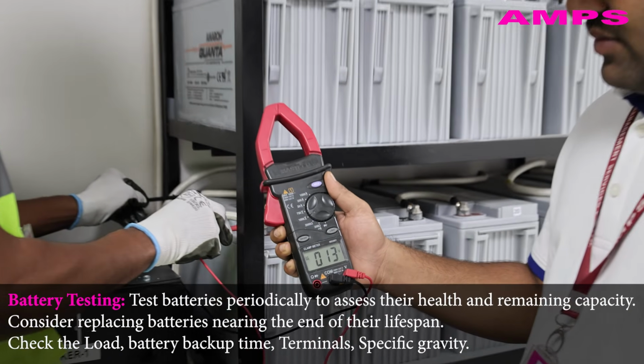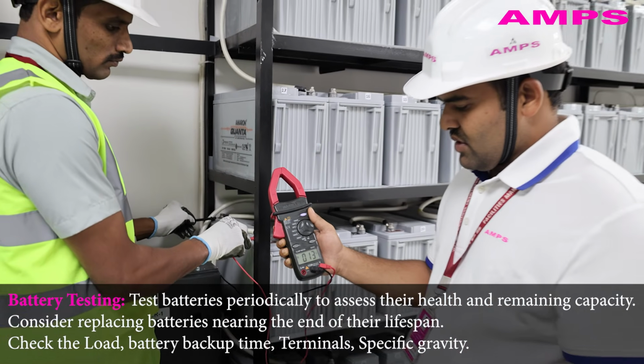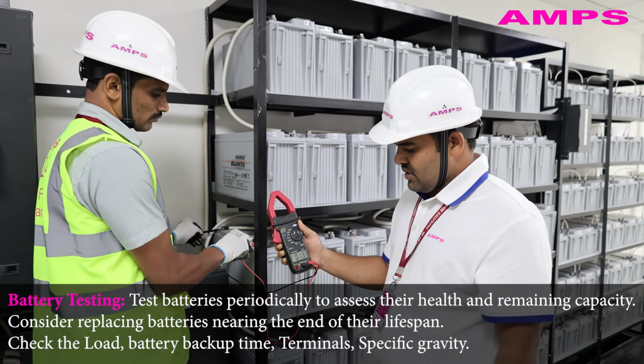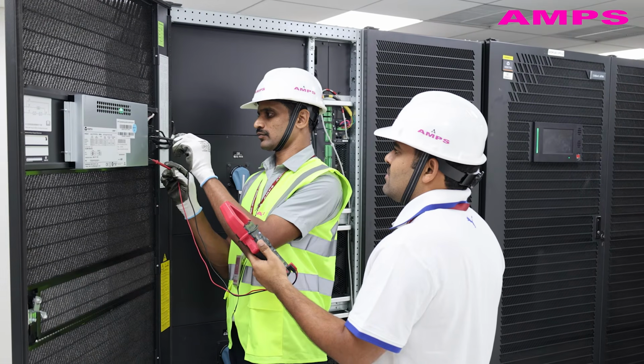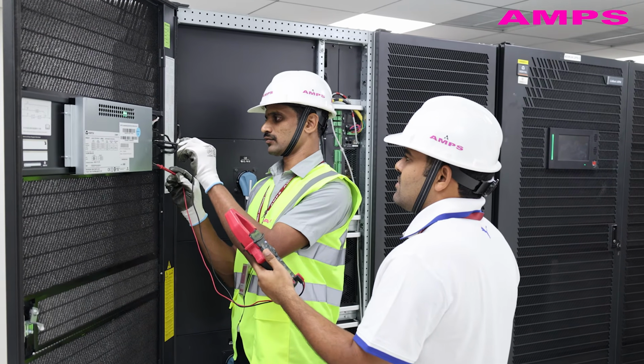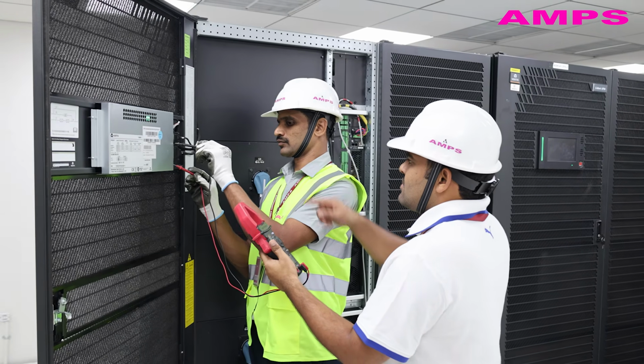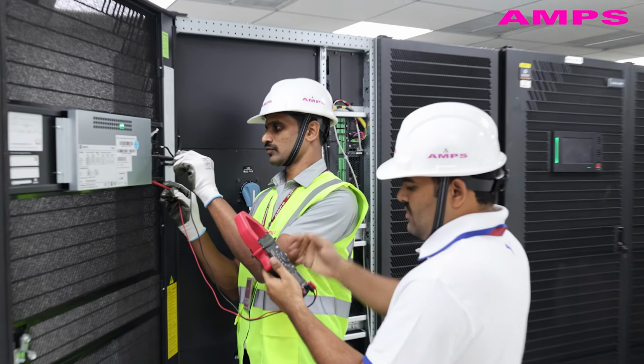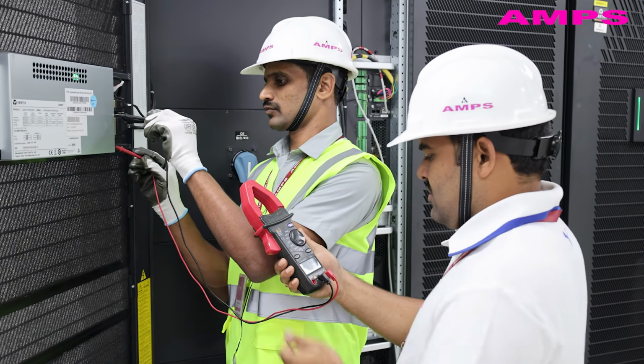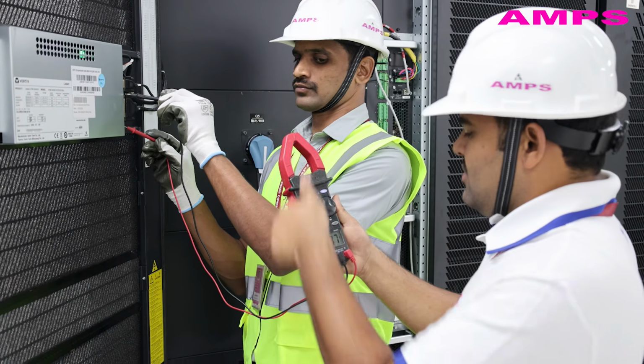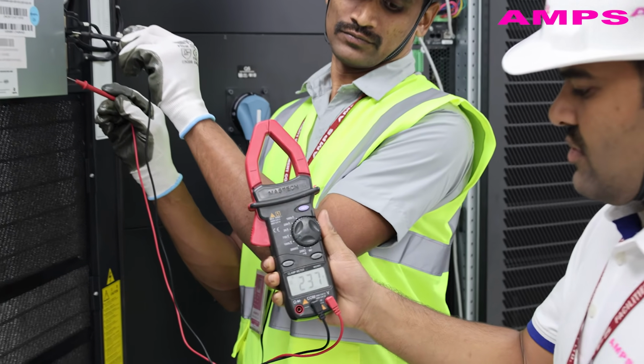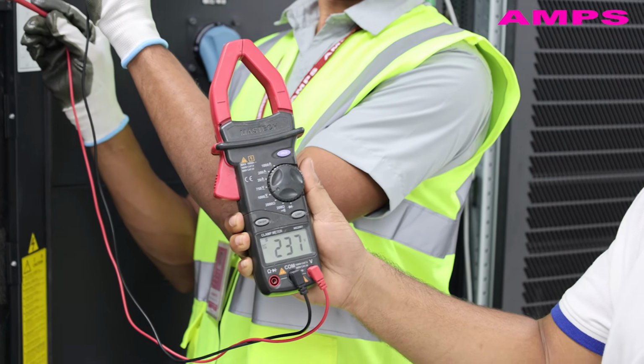Check the load, battery backup time, terminals, specific gravity, visual inspection, regularly check for dust buildup, signs of physical damage, and loose connections or overheating in cables. Test all the alarm functions and indicator lights to confirm whether critical alerts will be triggered properly.